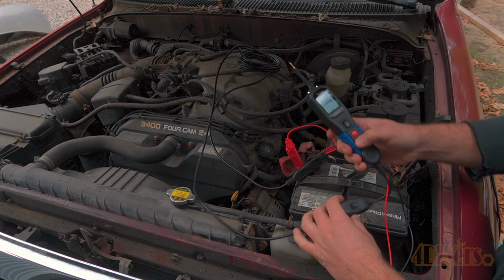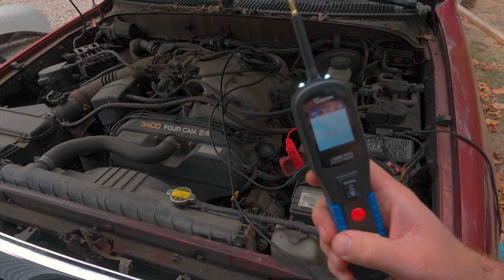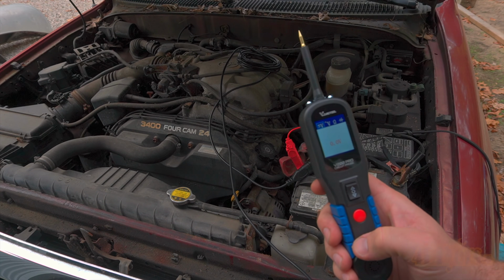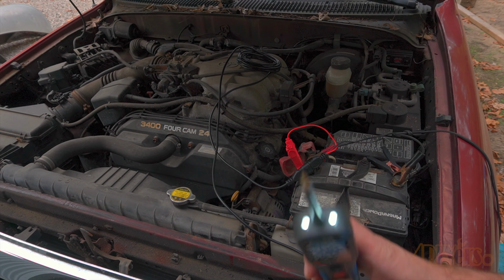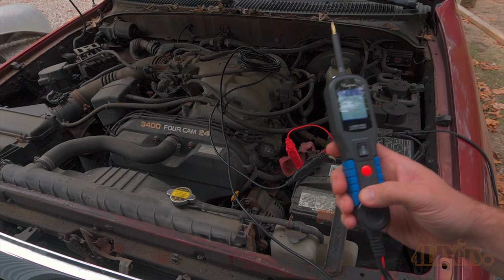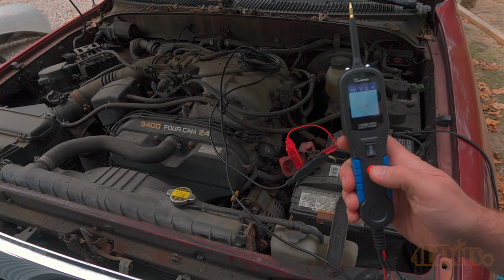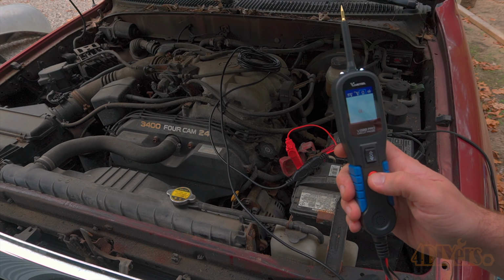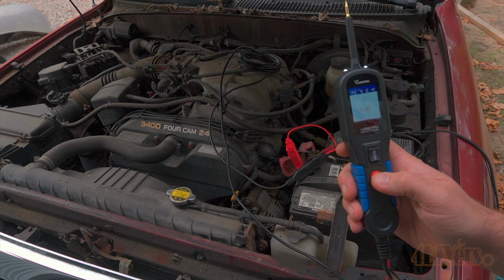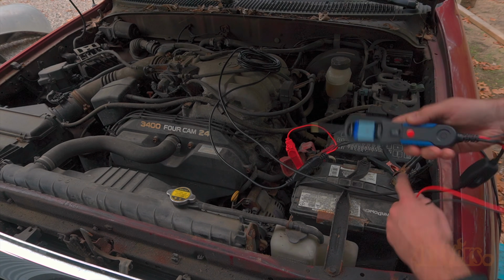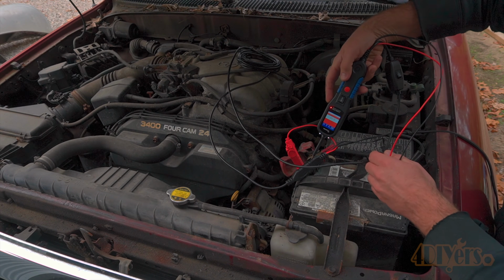Push the selector switch on the tester's cable to the number 1 position to turn on the tester. The LCD screen illuminates, and this will take a second to load. Once on, it defaults to the DC voltage setting. You can then use the red button to scroll through the different modes, each located at the top of the LCD screen.